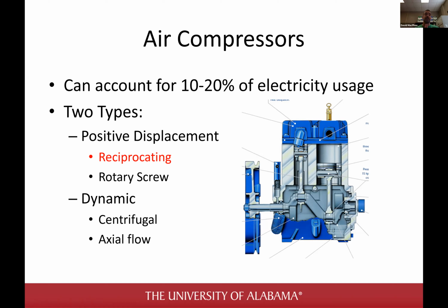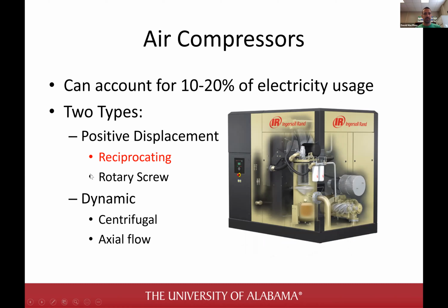However, they're really expensive to make in high air volume settings. You don't want to buy a giant 300 horsepower reciprocating air compressor - you want a rotary screw compressor instead. Almost every compressor that's between roughly 30 or 40 horsepower up to about 250 to 300 horsepower falls in this range.